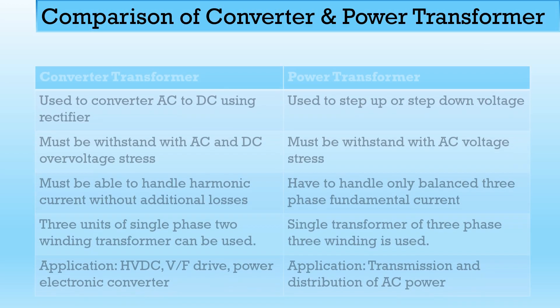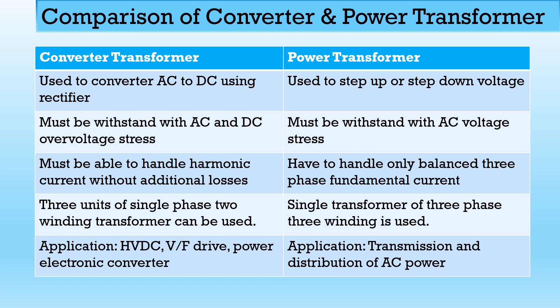Comparing the converter and power transformer: the converter transformer converts AC to DC using a rectifier, while the power transformer steps up or steps down voltage. The converter transformer must withstand combined AC and DC overvoltage stress, while the power transformer withstands AC voltage stress only. The converter transformer must handle harmonic current without additional losses; the power transformer handles only balanced three-phase fundamental current. The converter transformer uses three single-phase two-winding units, while a power transformer can use a single three-phase three-winding unit. Applications of the converter transformer include HVDC, VFD drives, and power electronic converters, whereas power transformer applications are AC transmission and distribution.